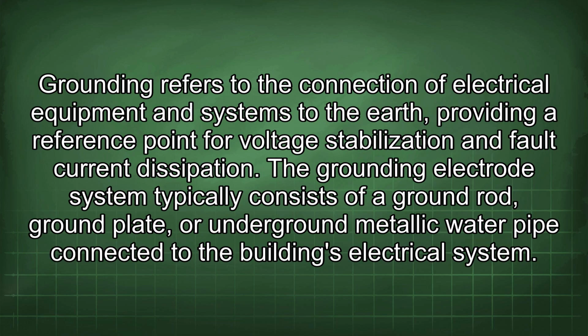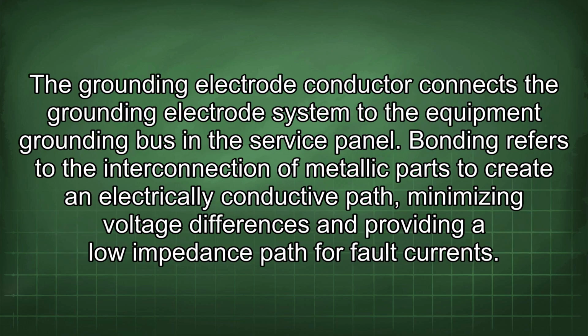Grounding refers to the connection of electrical equipment and systems to the earth, providing a reference point for voltage stabilization and fault current dissipation. The grounding electrode system typically consists of a ground rod, ground plate, or underground metallic water pipe connected to the building's electrical system. The grounding electrode conductor connects the grounding electrode system to the equipment grounding bus in the service panel.